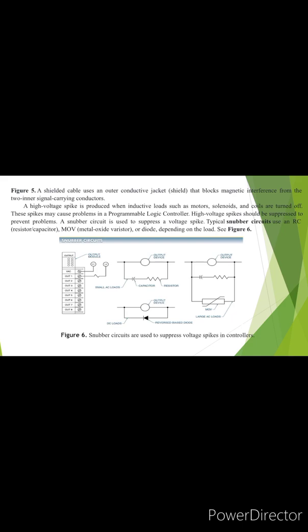Figure 5. A shielded cable uses an outer conductive jacket or shield that blocks magnetic interference from the two inner signal-carrying conductors. A high voltage spike is produced when inductive loads such as motors, solenoids, and coils are turned off. These spikes may cause problems in the programmable logic controller. High voltage spikes should be suppressed to prevent problems.